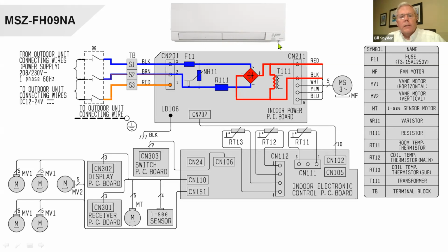And then this has got the i-see sensor down here, which rotates back and forth. So what we're looking at here is we're coming in with S1 and S2 with line voltage coming into the unit, and we're communicating between S2 and S3. You'll notice we come in here to this power module where we have AC volts coming in and DC volts coming out, and we're going to the fan motor with DC voltage, 5 wires going in, but it is 3-phase. So this fan motor has got the little board inside that's going to convert it back to AC.